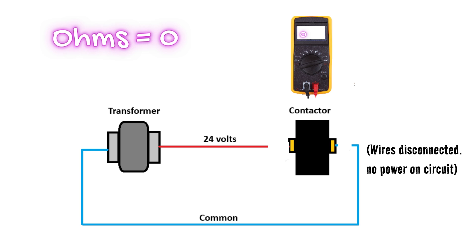You can also have a situation where your resistance value is very low. Let's say it's close to zero. That's an indication you have a short in that coil somewhere. The resistive value of that coil has completely been lost, and our current is allowed to travel so quickly that at this point we're probably tripping breakers or blowing fuses, or in this case, I have no protection on this circuit, so I'm probably burning out that transformer. You can also get a reading of OL, which is an open line or out of limits, which means you actually have a broken coil. It's physically separated, and you no longer have a complete circuit, and so you have no current draw whatsoever.